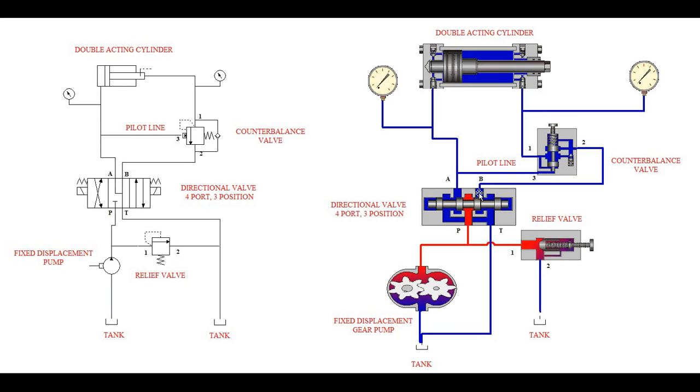At the same time, B is already exposed to T in the center position, but it would probably have a little bit less of a pressure drop because this spool would shift over more and make the passage from B to T that much less restrictive. So that's what's going on when the spool shifts left. When that happens and we put pressure and flow into port A, we know our cylinder is going to extend.